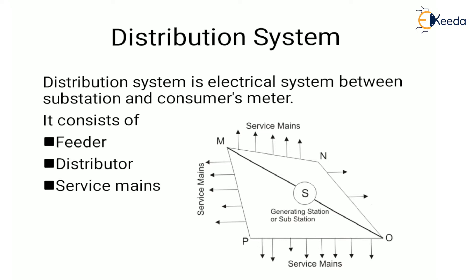On the feeder, no tappings are taken so that the current in it remains the same. The current carrying capacity is the main consideration while designing a feeder. Here SM and SO are the feeders. Next is the distributor — a distributor is a conductor from which tappings are taken out for supply to the consumer.